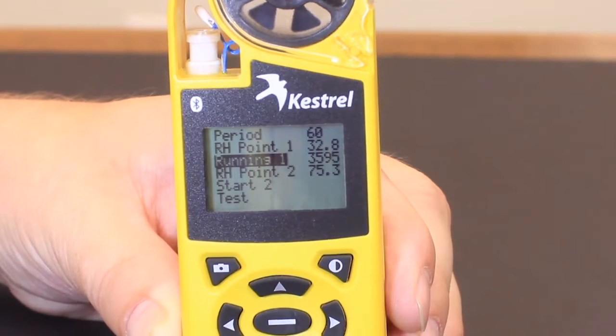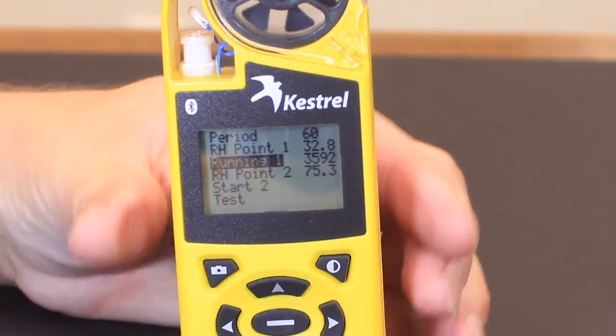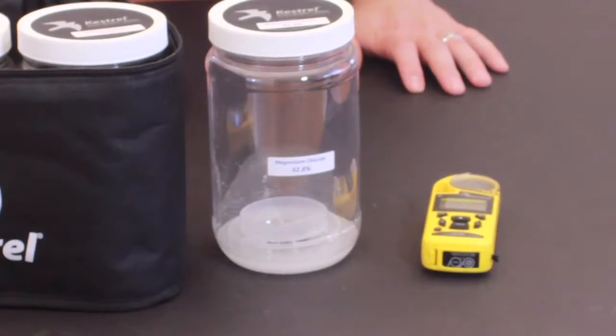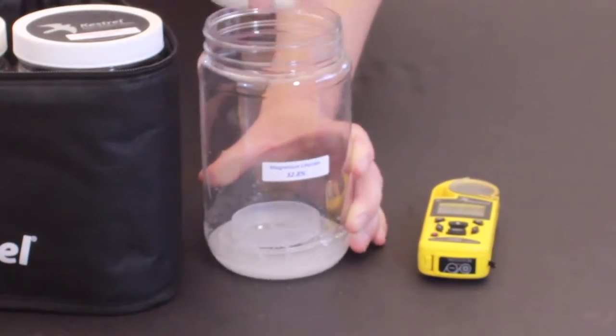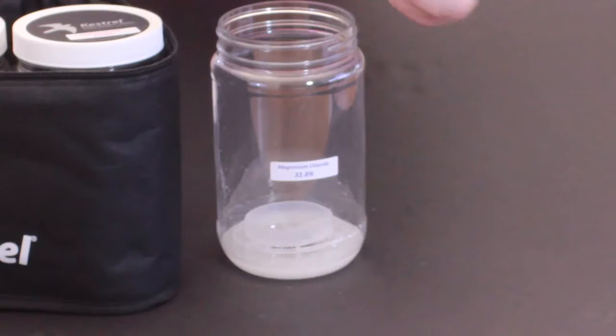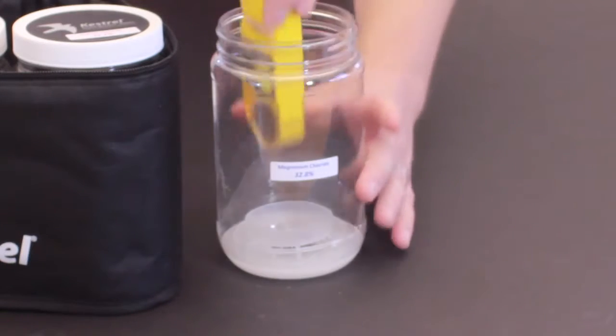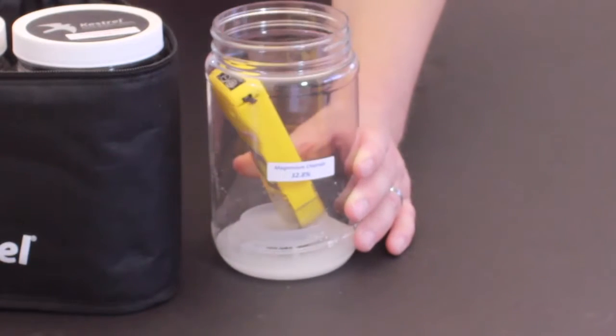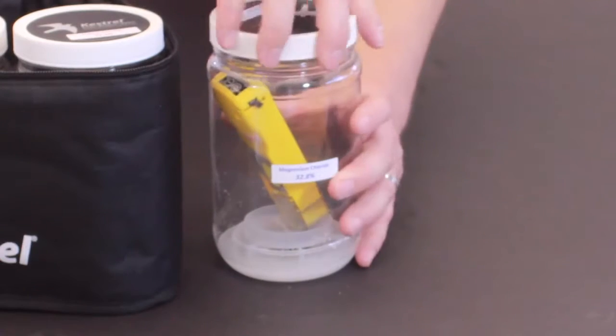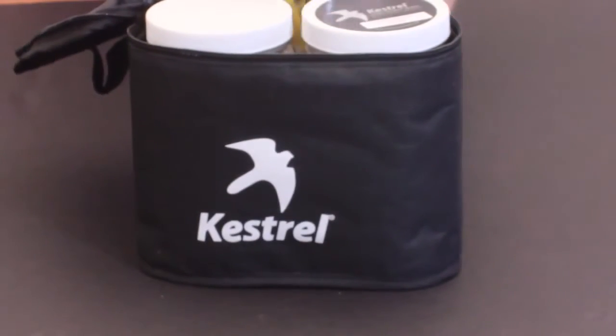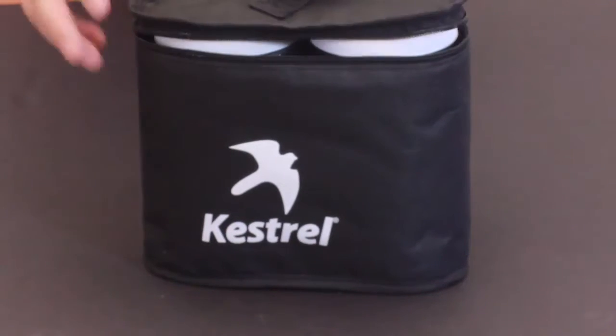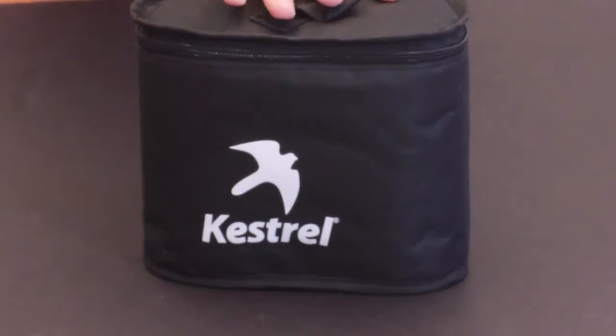So once the start one has started the countdown from 3600 seconds, let's open up the magnesium chloride chamber. We'd wrap it around here just to keep it out of the mixture. Close this lid tightly, and then we'll put it into our RH calibration kit. Zipper it up and leave it untouched for an hour.